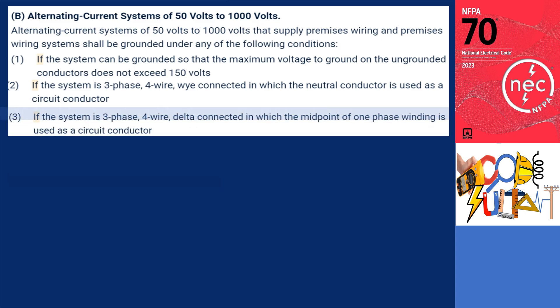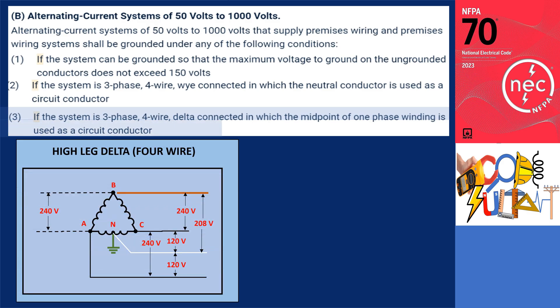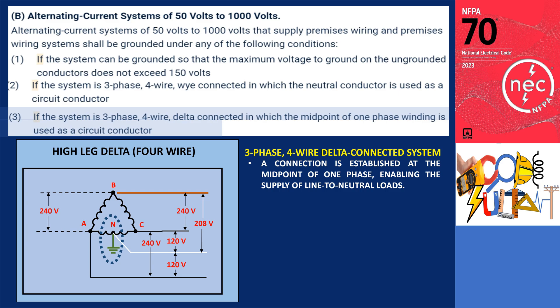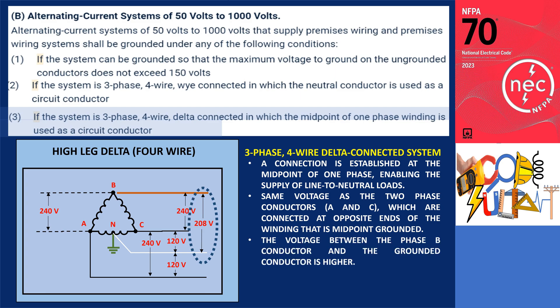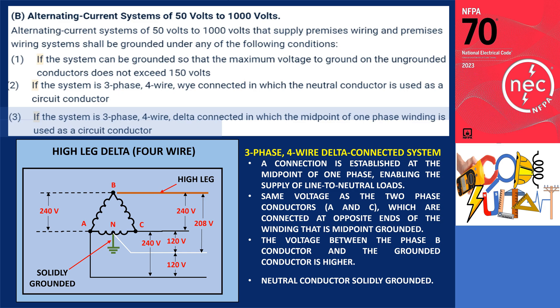For the third condition, if the system is three-phase, four-wire, delta-connected, and the midpoint of one-phase winding is used as a circuit conductor. The illustration depicts a three-phase, four-wire delta-connected system. In this system, a connection is established at the midpoint of one phase, enabling the supply of line-to-neutral loads. The grounded conductor in this configuration develops the same voltage as the two-phase conductors A and C, which are connected at opposite ends of the midpoint-grounded winding. The voltage between the phase B conductor and the grounded conductor is higher in this setup, and the code includes additional requirements addressing the arrangement and identification of the high leg. Same as with three-phase, four-wire Y-connected systems, the neutral conductor is utilized as a circuit conductor, necessitating that all operate with the neutral conductor solidly grounded.